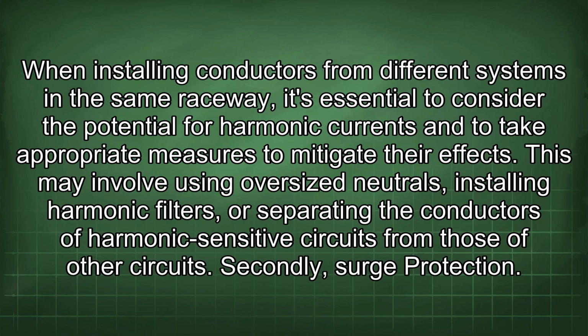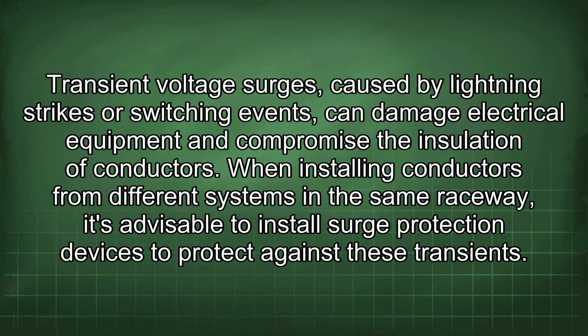When installing conductors from different systems in the same raceway, it's essential to consider the potential for harmonic currents and to take appropriate measures to mitigate their effects. This may involve using oversized neutrals, installing harmonic filters, or separating the conductors of harmonic-sensitive circuits from those of other circuits.